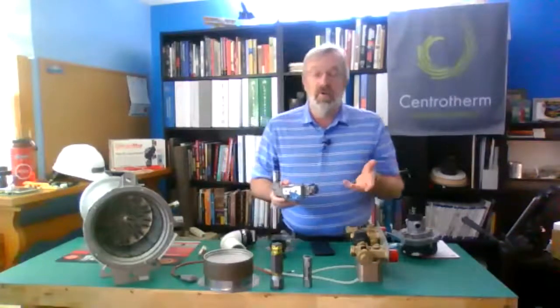So if I have that, stop right there. Let's get that corrected. That could be a gas meter hanging up. That could be a regulator hanging up. It could be any of those things. If it's a brand new installation, we might take a quick look at our gas pipe sizing, make sure that we've sized it appropriately and we've done the correct thing.